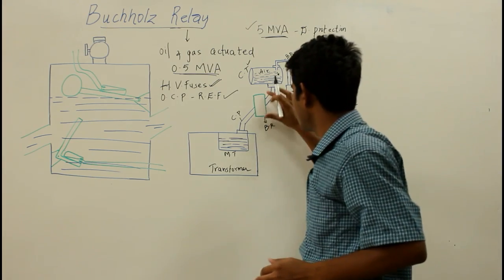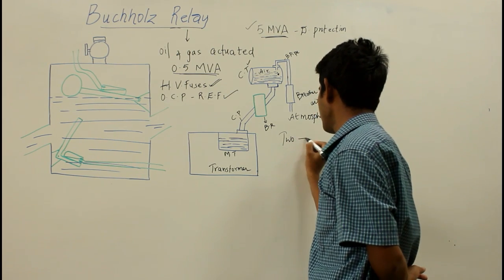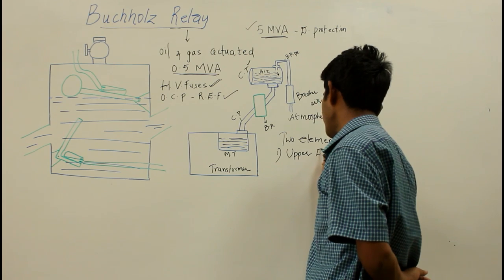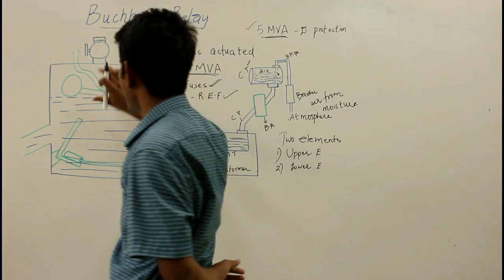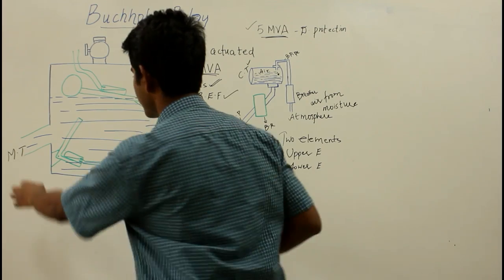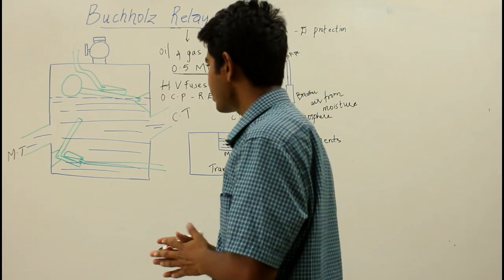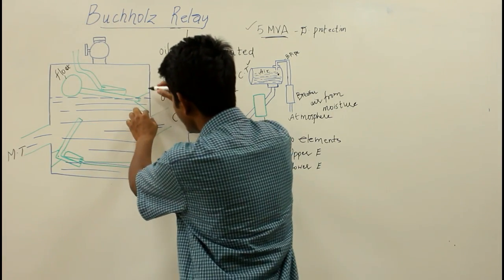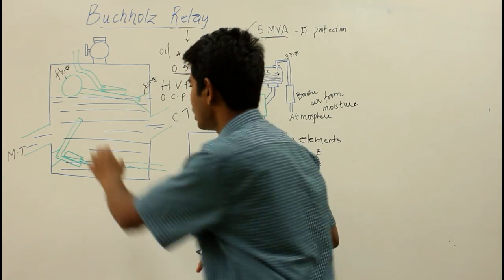Now discussing the construction of the Buchholz relay: it mainly consists of two elements — the upper element and the lower element. The upper element is on the conservator tank side and the lower element is on the main tank inlet side. The upper element consists of a float attached to a hinge in such a way that it can move up and down depending on the oil level.